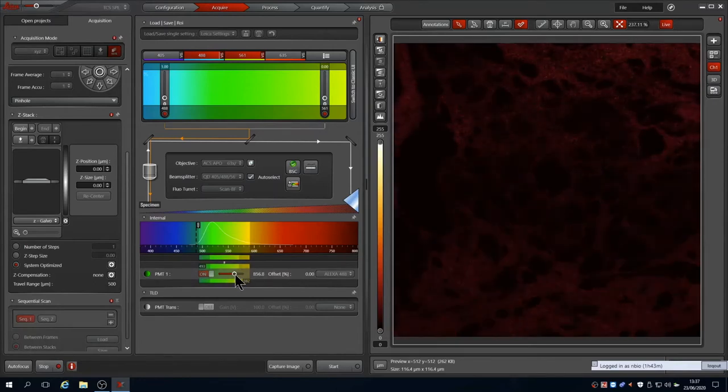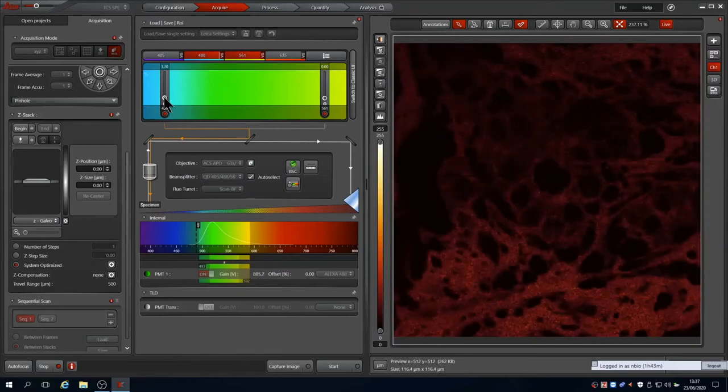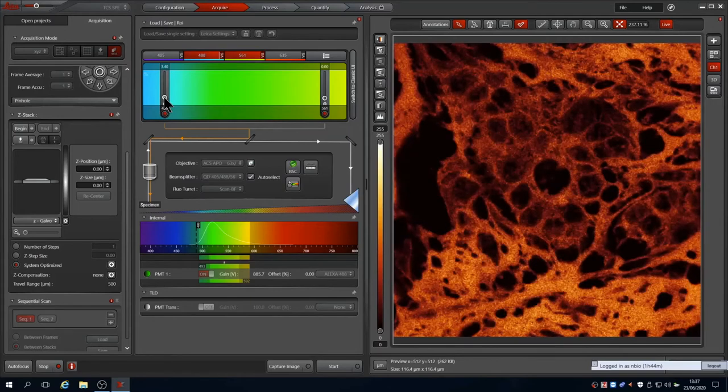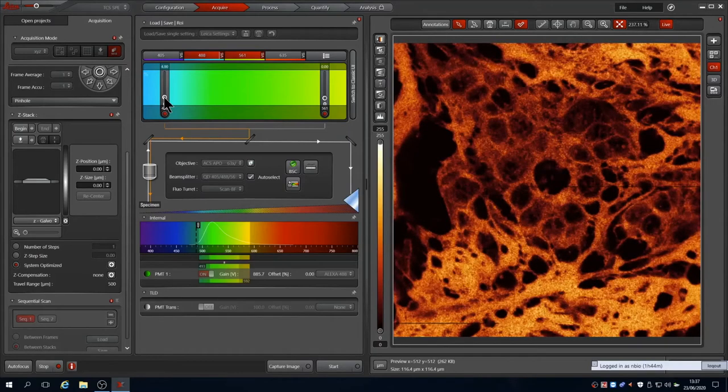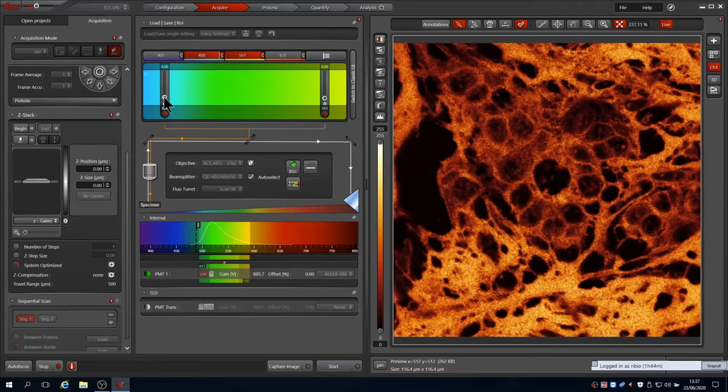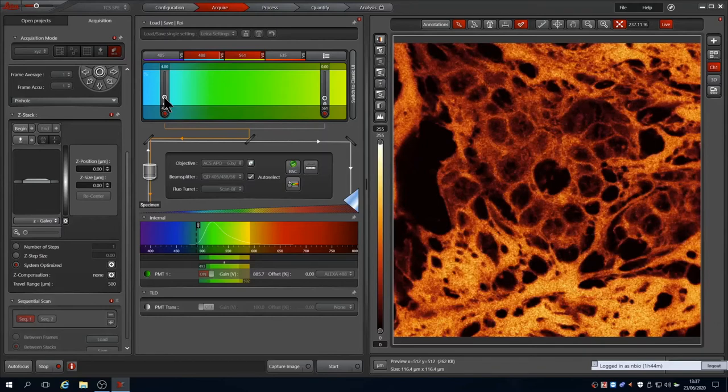The system remembers that we had the range indicator LUT on for the live image, so there is no need to adjust that. I increase the gain first as before. Here I have gone to almost 900V. You can see that the noise isn't too bad. It is generally worth keeping gain below 900V if possible. As you approach 1000V and higher, you detect the sensitivity becomes very non-linear, which means you cannot reliably compare intensities between samples in such cases.